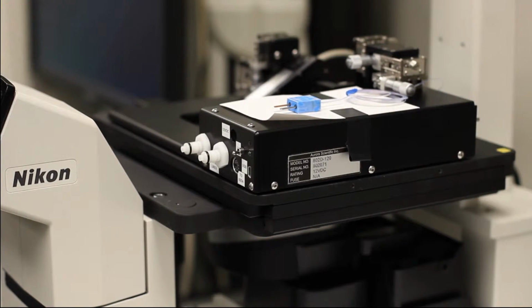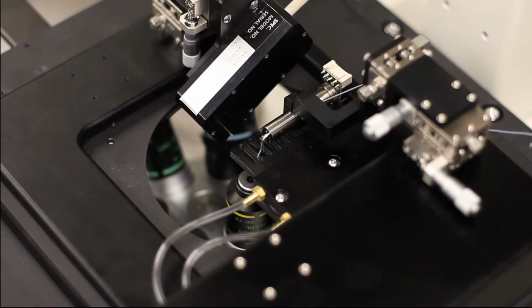Align the 802D such that the bath plate itself is centered within the stage cutout of your microscope. The plate is designed to fit into a standard 100 mm cutout. However, some adjustment will likely be required to ensure interference-free movement.